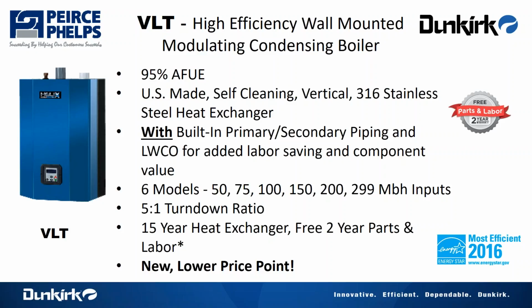So again, the price point on this, we showed that slide that had all those manufacturers in it. This market is very competitive. So we've adjusted this boiler, the VLT, is at or just above comparable condensing models that do not have built-in primary, secondary piping and low water cutoff. They're basically getting it for free, and they're going to be saving about 4 to 8 hours of time on the job. So we equate that to over $600 of added value. So again, encourage you to price this boiler and see where that falls with any brand you're using now.